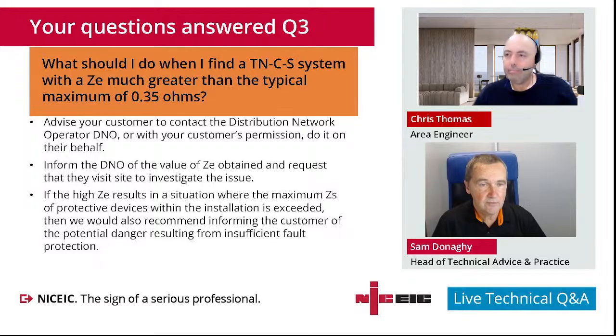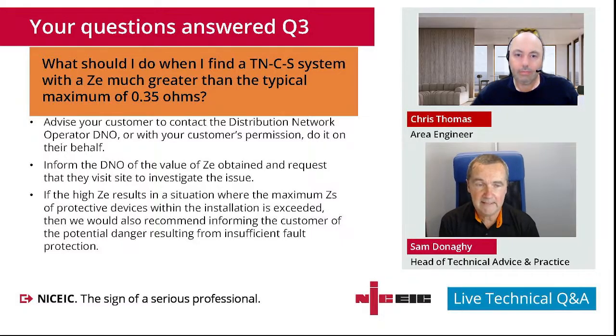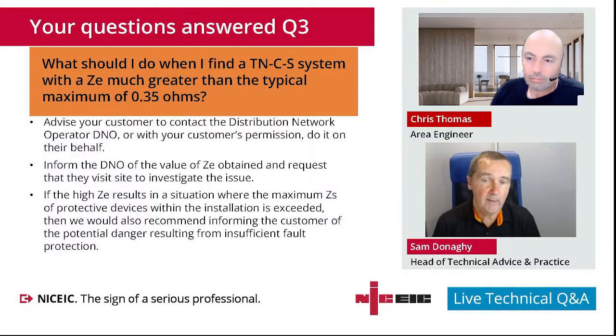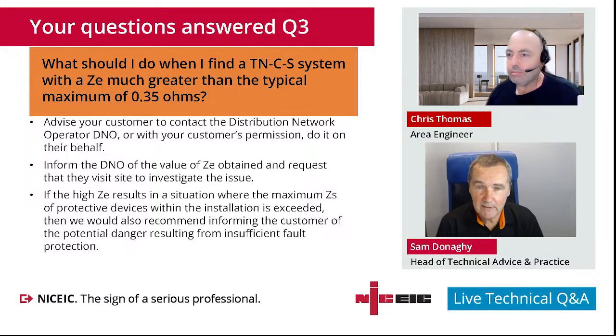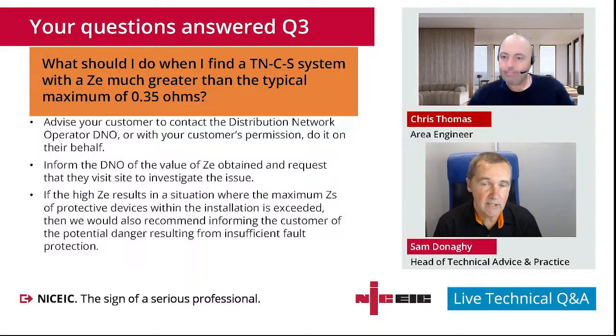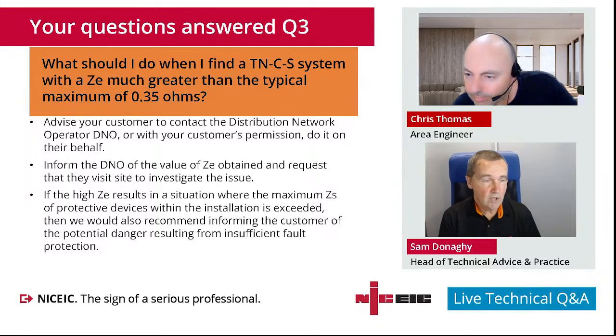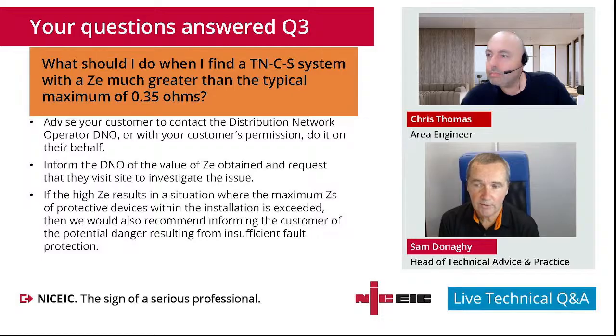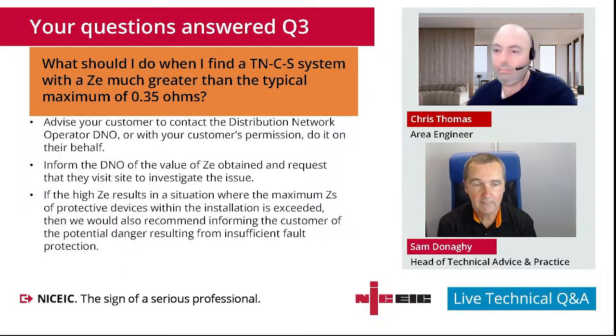They're typical values that are given by the DNO to enable design to be carried out when the supply isn't there. So on a brand new installation, when the installation is being designed without the supply being present, those values are given by all DNOs to enable the designer to do their calculations to determine required cable size for cable length, etc. So those values aren't a hard maximum that they can't exceed. They are typical values that they give out for design purposes. So that's why they don't have to come and make the changes.